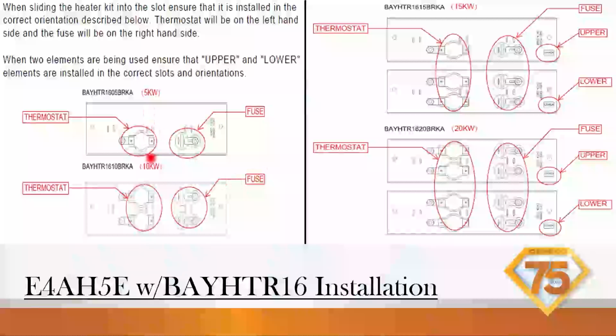Here's the 5 kW, 10 kW, 15, and 20. So you've got your double stacks, you've got your fuses. Notice the upper and lower. Once you have the single 5 and 10 kW, you're going to use the upper. But with a 20 and a 15, as you can see, it is labeled upper, lower. So it is kind of fail safe. They only go in one way for proper function.